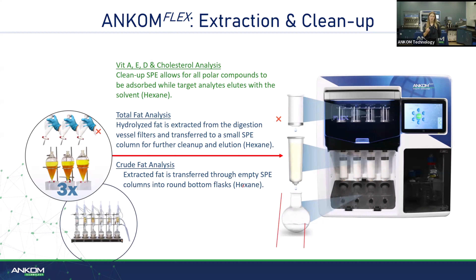For crude fat analysis, you would use essentially an empty SPE column, so there would be no sorbent material in it because it is not needed. From the digestion vessel, your fat would just travel through the empty column into your round bottom flask. And then the evaporation oven is where, under low temperature and positive flow nitrogen, your solvent is evaporated, leaving you your analyte. For vitamins, you would then reconstitute this with your preferred solvent and move on to your quantitative step on your HPLC or your mass spec.